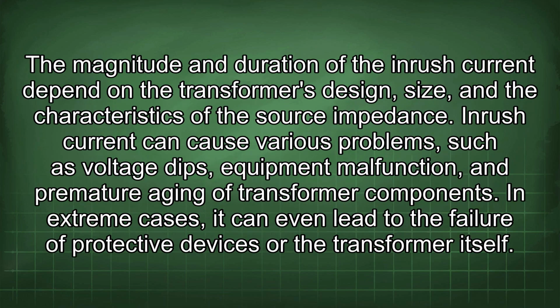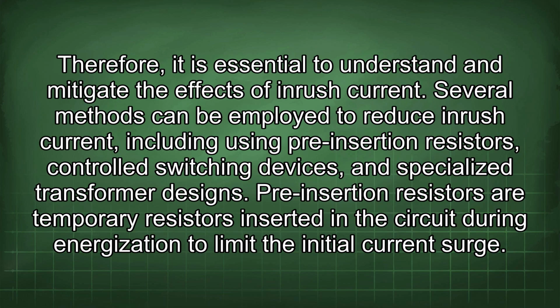The magnitude and duration of the inrush current depend on the transformer's design, size, and the characteristics of the source impedance. Inrush current can cause various problems, such as voltage dips, equipment malfunction, and premature aging of transformer components. In extreme cases, it can even lead to the failure of protective devices or the transformer itself. Therefore, it is essential to understand and mitigate the effects of inrush current.